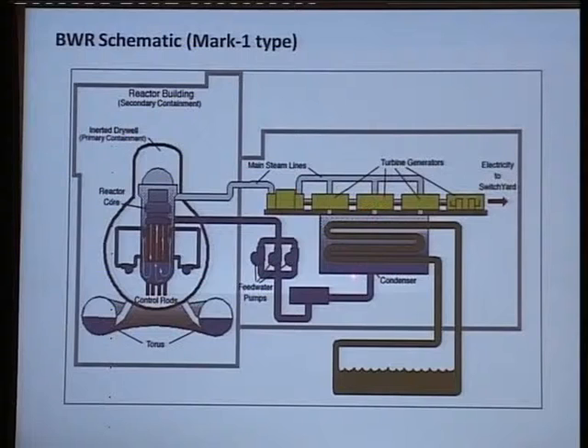Then the steam comes into a condenser where it's cooled by seawater or cooling towers, and the condensate goes back into the reactor. In addition, in this design, there is a toroidal vessel made of steel, or concrete lined with steel, filled with water. The purpose of this vessel is that if pressure builds up in the drywell, the air and steam mixture are forced to go through the water. The steam condenses, energy transfer takes place, the pressure comes down, and the air communicates with the rest of the building at relatively low pressure, and it doesn't go into the environment.